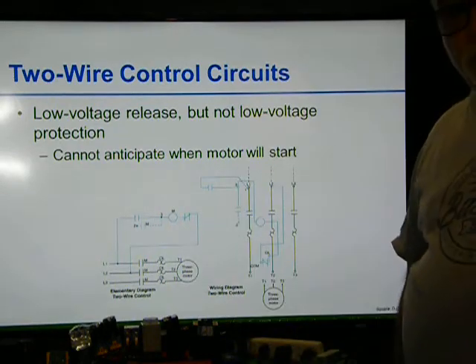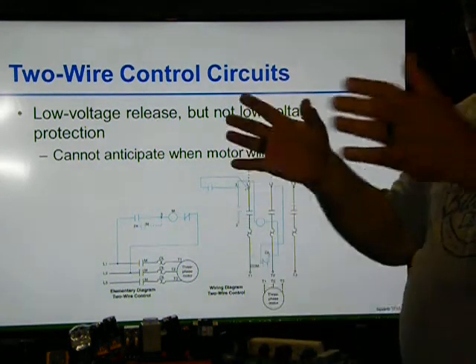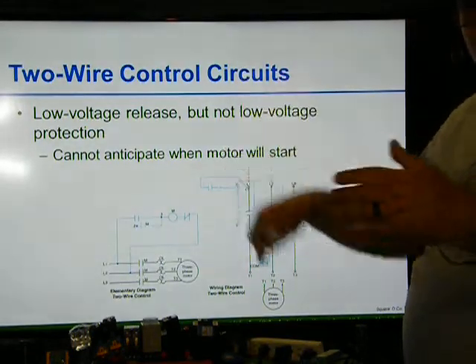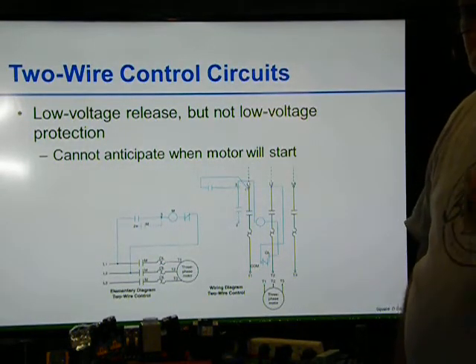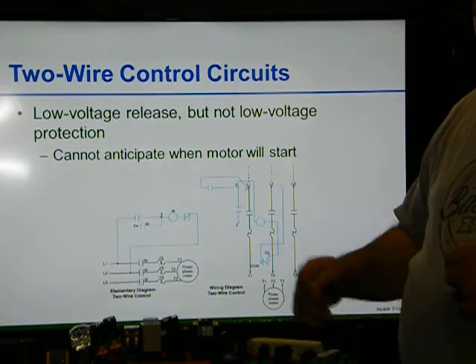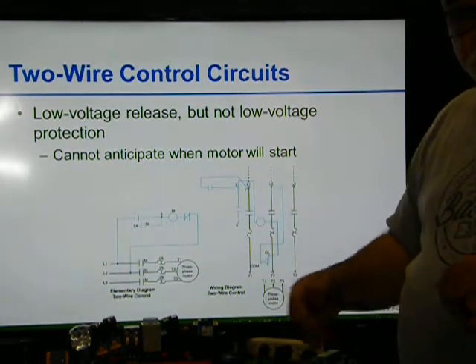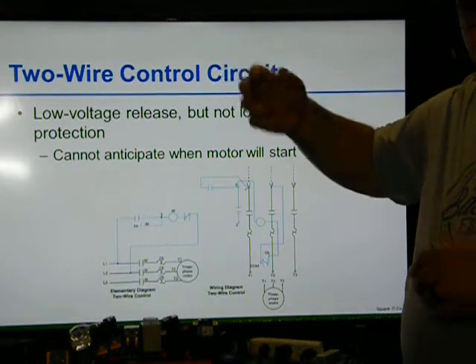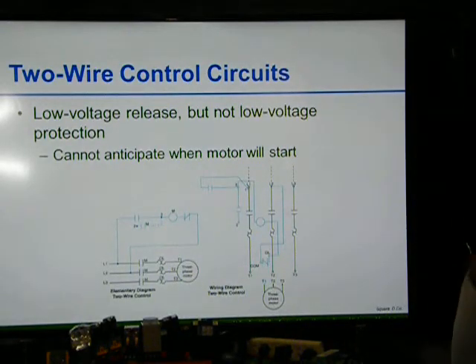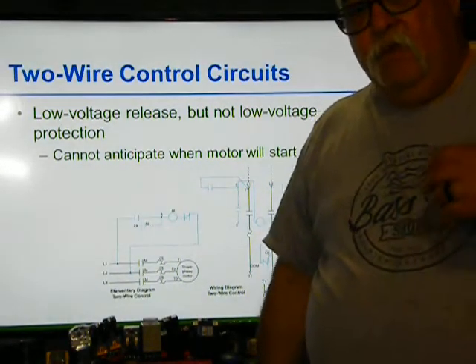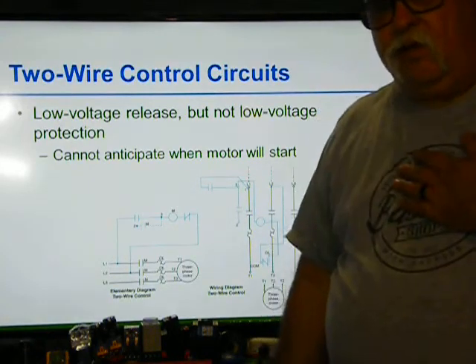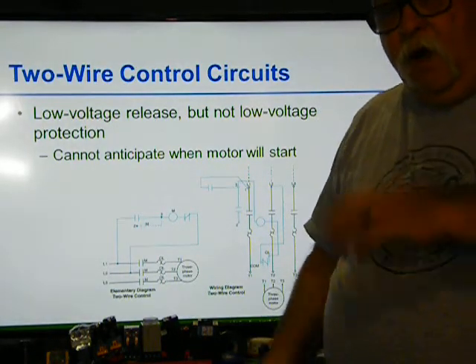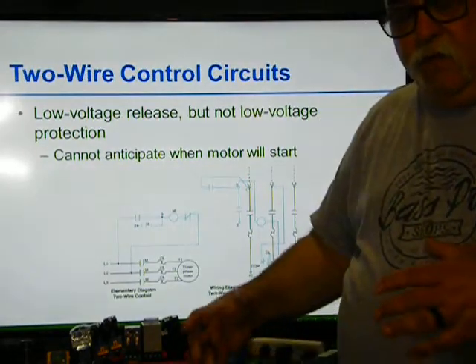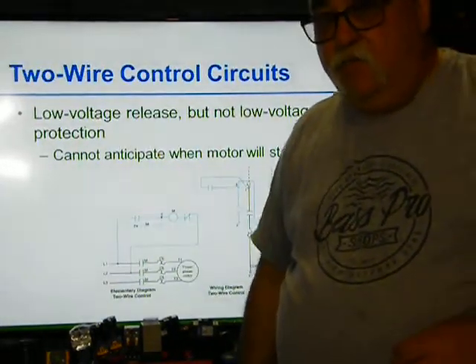But when power comes back on, we want that exhaust fan to work, because it controlled the fume hood where they had no control down below. The fume hood had to run 24/7, so somebody wouldn't walk away. If they were working on an experiment, they wanted to make sure they couldn't turn the exhaust off, so in case they left something there, it's still exhausting. So we had them wired before they had control, and we turned around and rewired them so they had no control. So they were always on. We had control and we had to work on it, but the person operating inside the fume hood didn't. That was for safety reasons that we took them off.